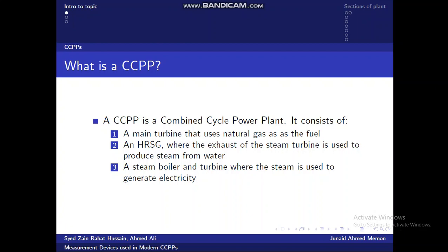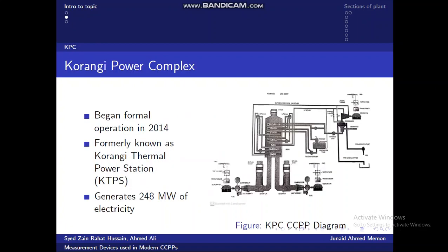So K Electric states that it increases by up to 5%, which sounds like a really small number, but they also say that this saves them about 6 million cubic feet of oil annually. So it's a big saving. So KPC began formal operation in 2014. It was constructed in 2012, and it was formerly known as the Korangi Thermal Power Station, or KTPS. It generates 248 megawatts of electricity, so there are 4 turbines present, 2 gas and 2 steam. The gas turbines produce 100 megawatts each, and the steam turbines produce 24 megawatts each.